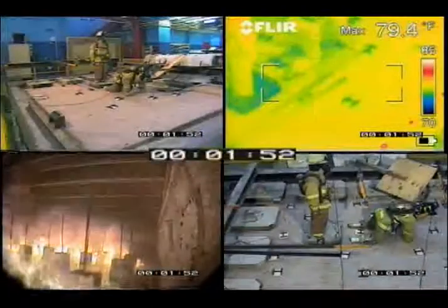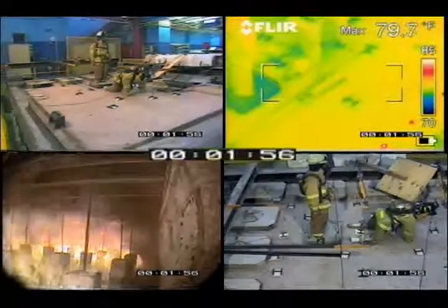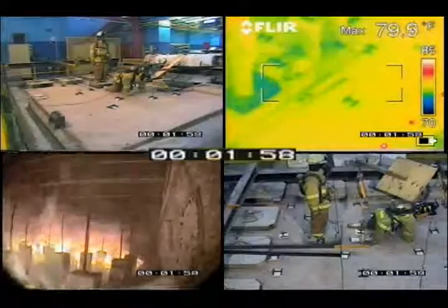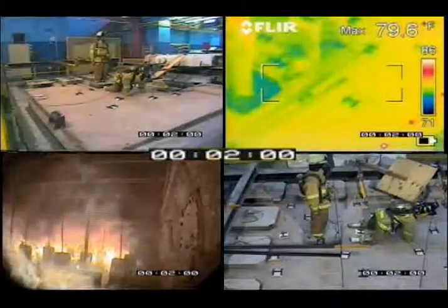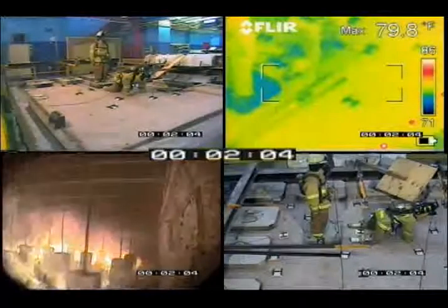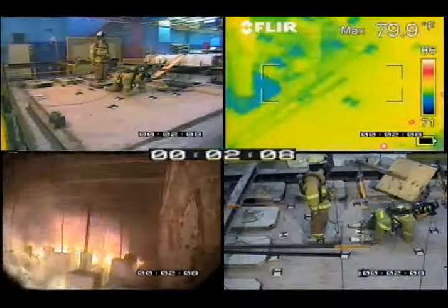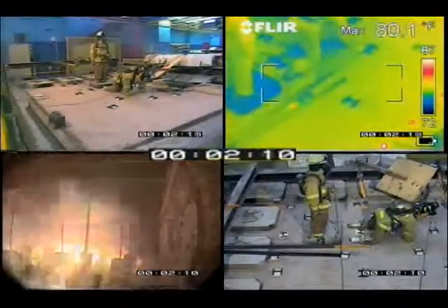2 minutes into the test, smoke is visible emitting from breaches in the fire stopping seal between the perimeter test frame and the floor. 3 small breaches are visible at the bottom of the TIC view. UL staff note the floor assembly beginning to vibrate, but the vibrations are not yet observable in the camera view.